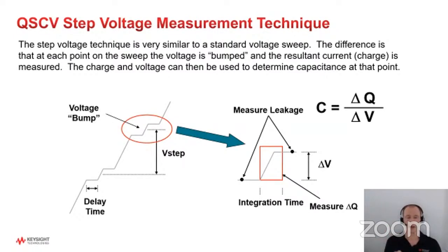And that bump creates that delta V, which creates a change in the charge stored in the capacitor, a delta Q. Now you can measure that charge by monitoring the current going into the device. And if you know the time, of course, you can average it out and calculate the delta Q. And then using the basic equation I talked about earlier, C equals Q over V, we can calculate capacitance at each point along the curve as we sweep.